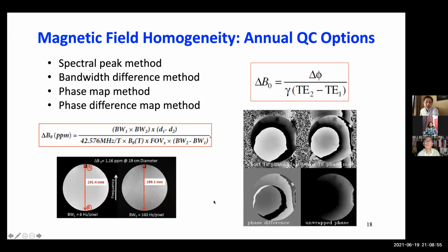So those are the vendor's measurements. How do we make measurements as a physicist? Both AAPM and ACR recommend 4 methods. The easiest method is the spectral peak method. We just put the homogeneous phantom there and get a spectrum, and then look at the full width at half maximum. If we do a little bit more, we can use the bandwidth difference method. The bandwidth difference method involves doing 2 images with the same setup but different bandwidth, measuring the diameter of the image, and then plugging into this equation, and we can get the overall homogeneity.